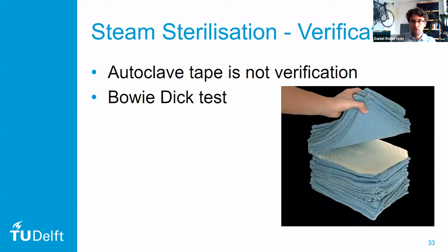Now, the most classical form of process verification is with something called a Bowie and Dick test. This is actually quite a simple test that can be performed. It's a stack of cotton sheets, and in the middle of those cotton sheets, we have an indicator sheet. This indicator sheet is quite similar to autoclave tape. We have a bundle of these cotton sheets with the indicator sheet in between, and when the autoclave has run its cycle, we look at this sheet, and only when the sheet has completely changed color, we know that the sterilization was successful.